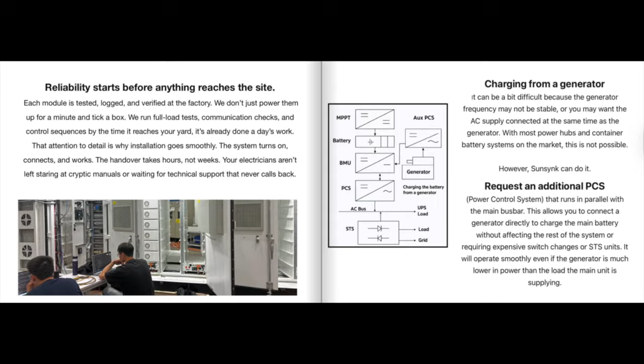You have two solutions. One, you can use the ATS and charge in the conventional manner, for sure, that can work. The second solution is we add a second PCS, power control system. And the second PCS is directly connected to the battery. If you see the diagram on the right-hand side, you'll see the MPPTs join the battery. And the battery, through the BMU, goes to the PCS, goes to the AC bus, and goes into the STS like before. However, we have an auxiliary, a second PCS, a second inverter. And that secondary inverter will charge the batteries directly from the generator.